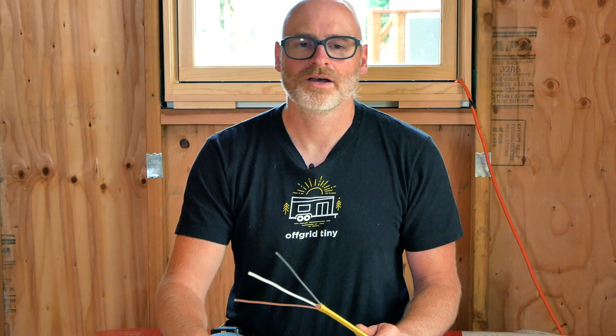Now, a mistake that I'm just catching right now while I'm talking about this is that I forgot to label the white wire here on this 240 volt circuit. Anytime you're running standard 2-wire like this, 240, you have to label the white wire black on both ends to signal that this is also a hot conductor. So imagining that this is not here, you could think of this as just a 30 amp 110 panel over here, and we've got 4 different circuits.